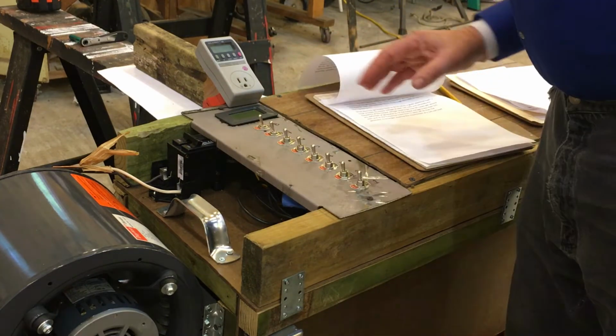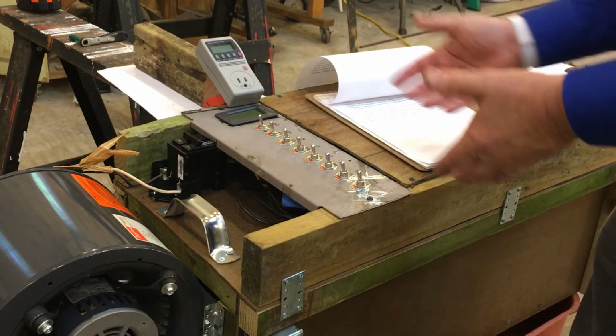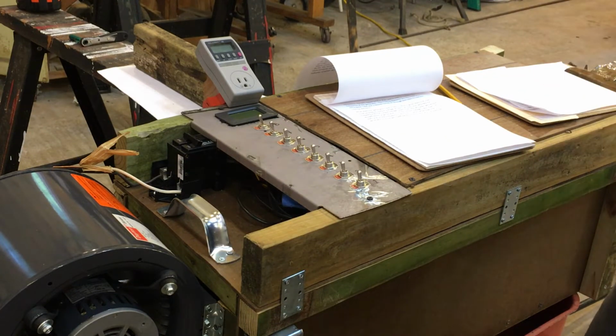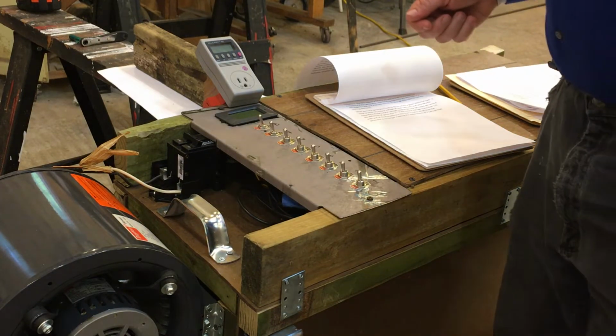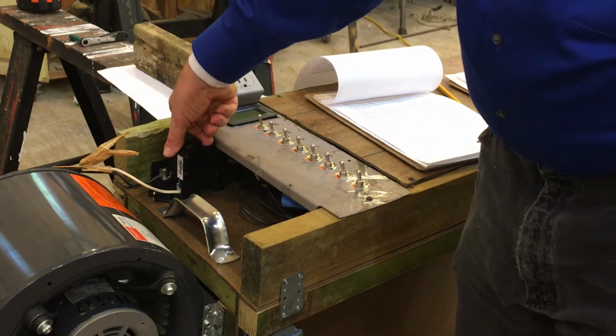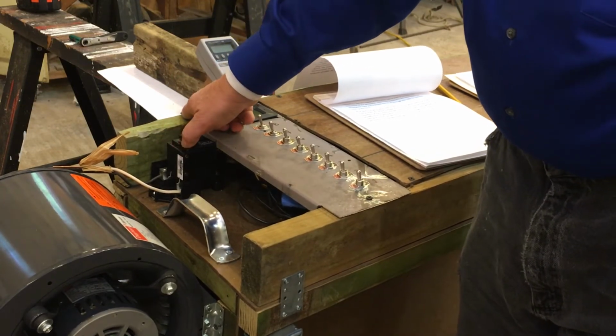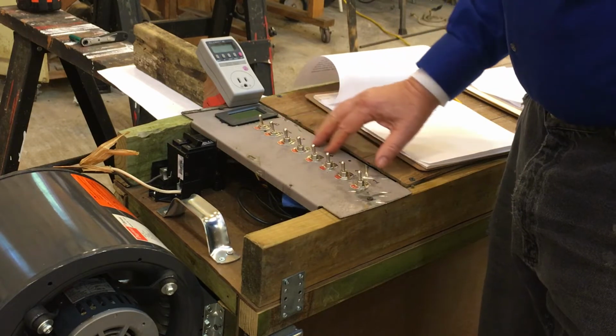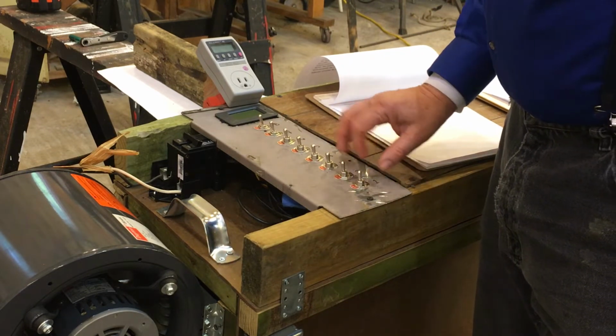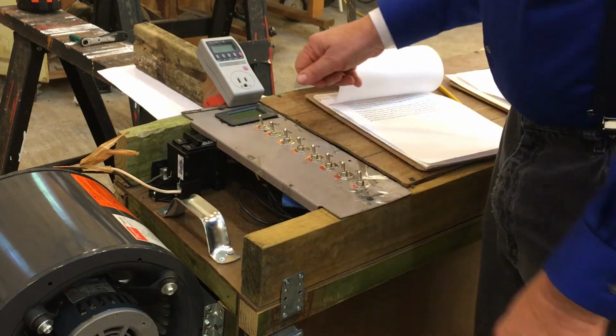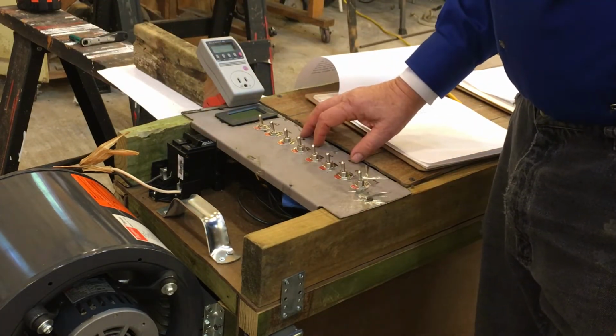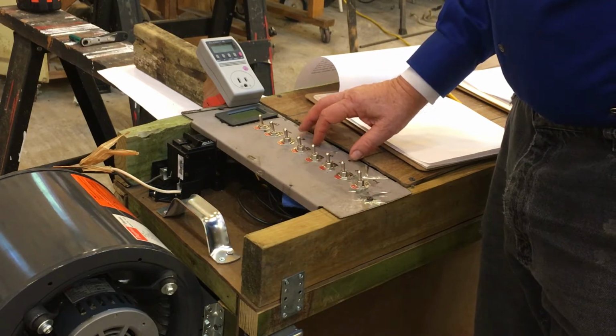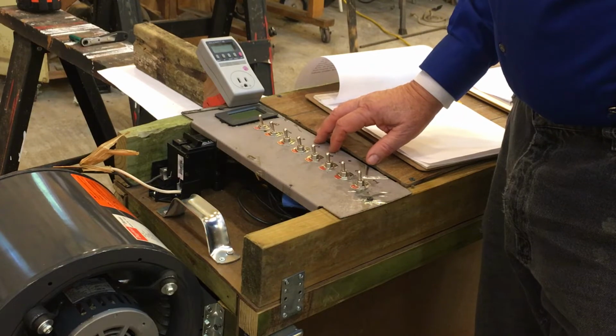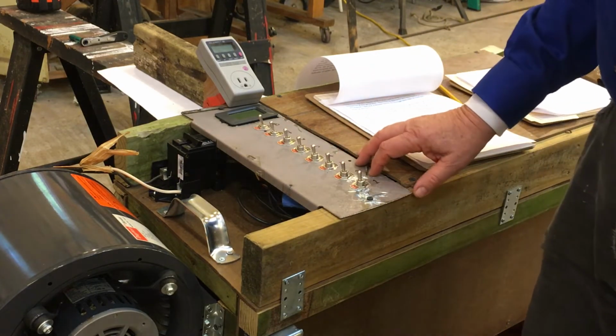So as we move forward, I usually will read the meter, probably write down what it's doing, then move to a new load, apply the load, and so forth as we make our way through. And you will notice, actually, as I do this, that I am applying the load and then removing the load, setting my switches. My switches have turned out to be a little too light for the load, so I don't switch them under load. I go ahead and set them up and then reapply the load. This, of course, is just the first generation of load bank system. I'm going to have to try to make some improvements to make that a little easier to use.